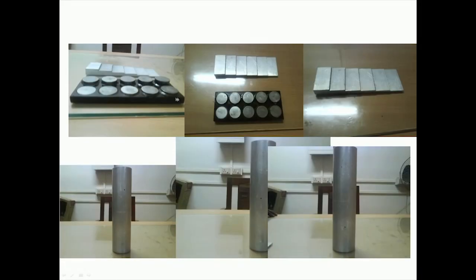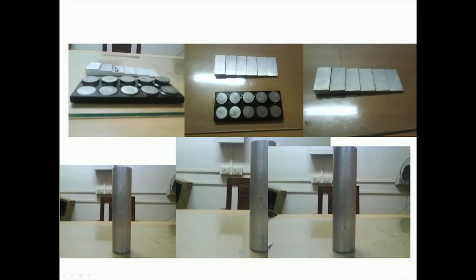Then you could have this kind of blocks also. For example, if you see this one over here. Okay. So this has several steps like this. These steps have different thicknesses. So that means this kind of block can be used for thickness calibration. In cases where you know that there is some material loss or material thinning, and if you want to inspect that kind of damage by using ultrasonic testing, then these kinds of blocks are quite useful to calibrate the instrument before you do that test.